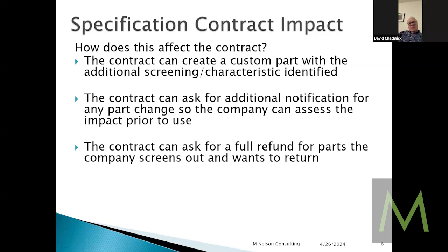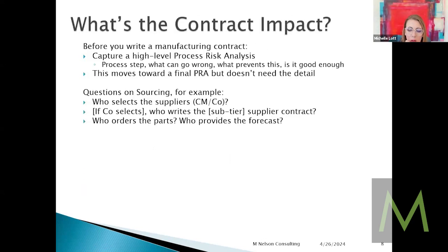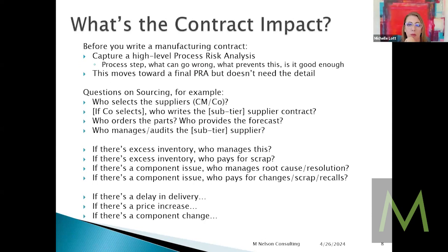Yes. Agreed. And if I can just expound on David's point there about the QSR, it's going to get even more complicated for supplier management with QMSR that comes into effect in 2026. That's because they have defined customer property now as being required to be addressed. I think I'm going to email them about this. I cannot figure out what they mean, because in the comment about what customer property means, it says, for example, a manufacturer is expected to ensure that the integrity of a component provided by a contract manufacturer is not compromised before it is incorporated into the device being manufactured.